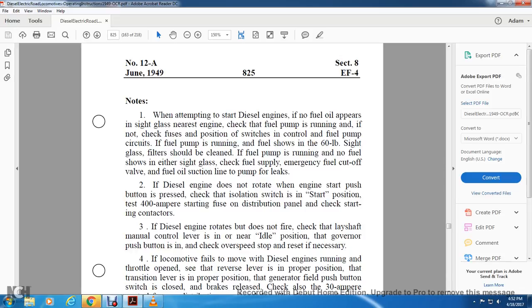If not, check the fuse and the position of the switch for the control fuel pump. Check if the fuel pump is running. Fuel should show in the 60-pound sight glass. The filter should be clean. If the fuel pump is running but no fuel shows in either sight glass, check the fuel pump supply, the fuel cutoff valve, and the fuel oil suction line of the pump for leaks.